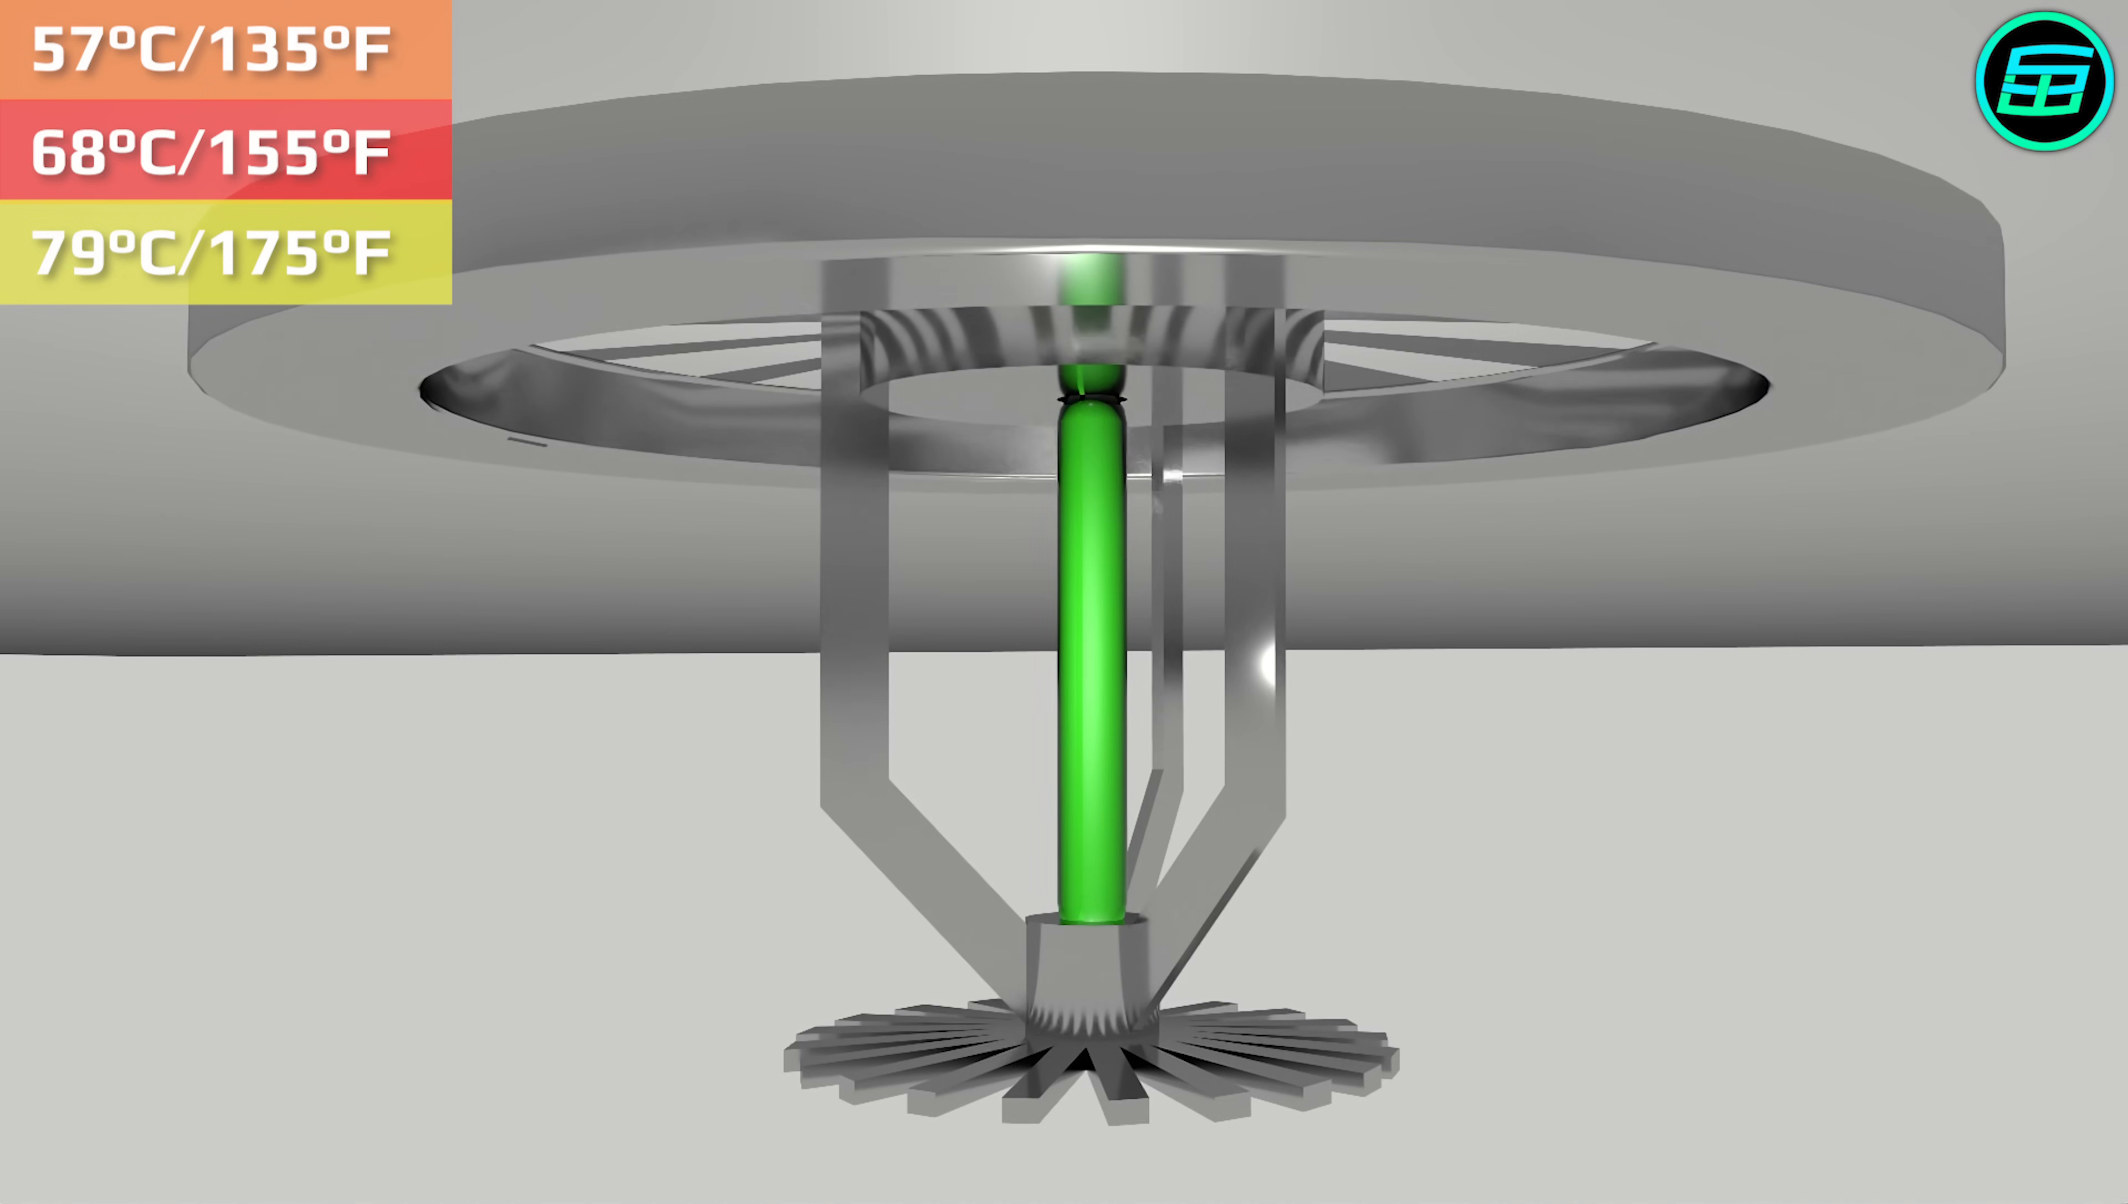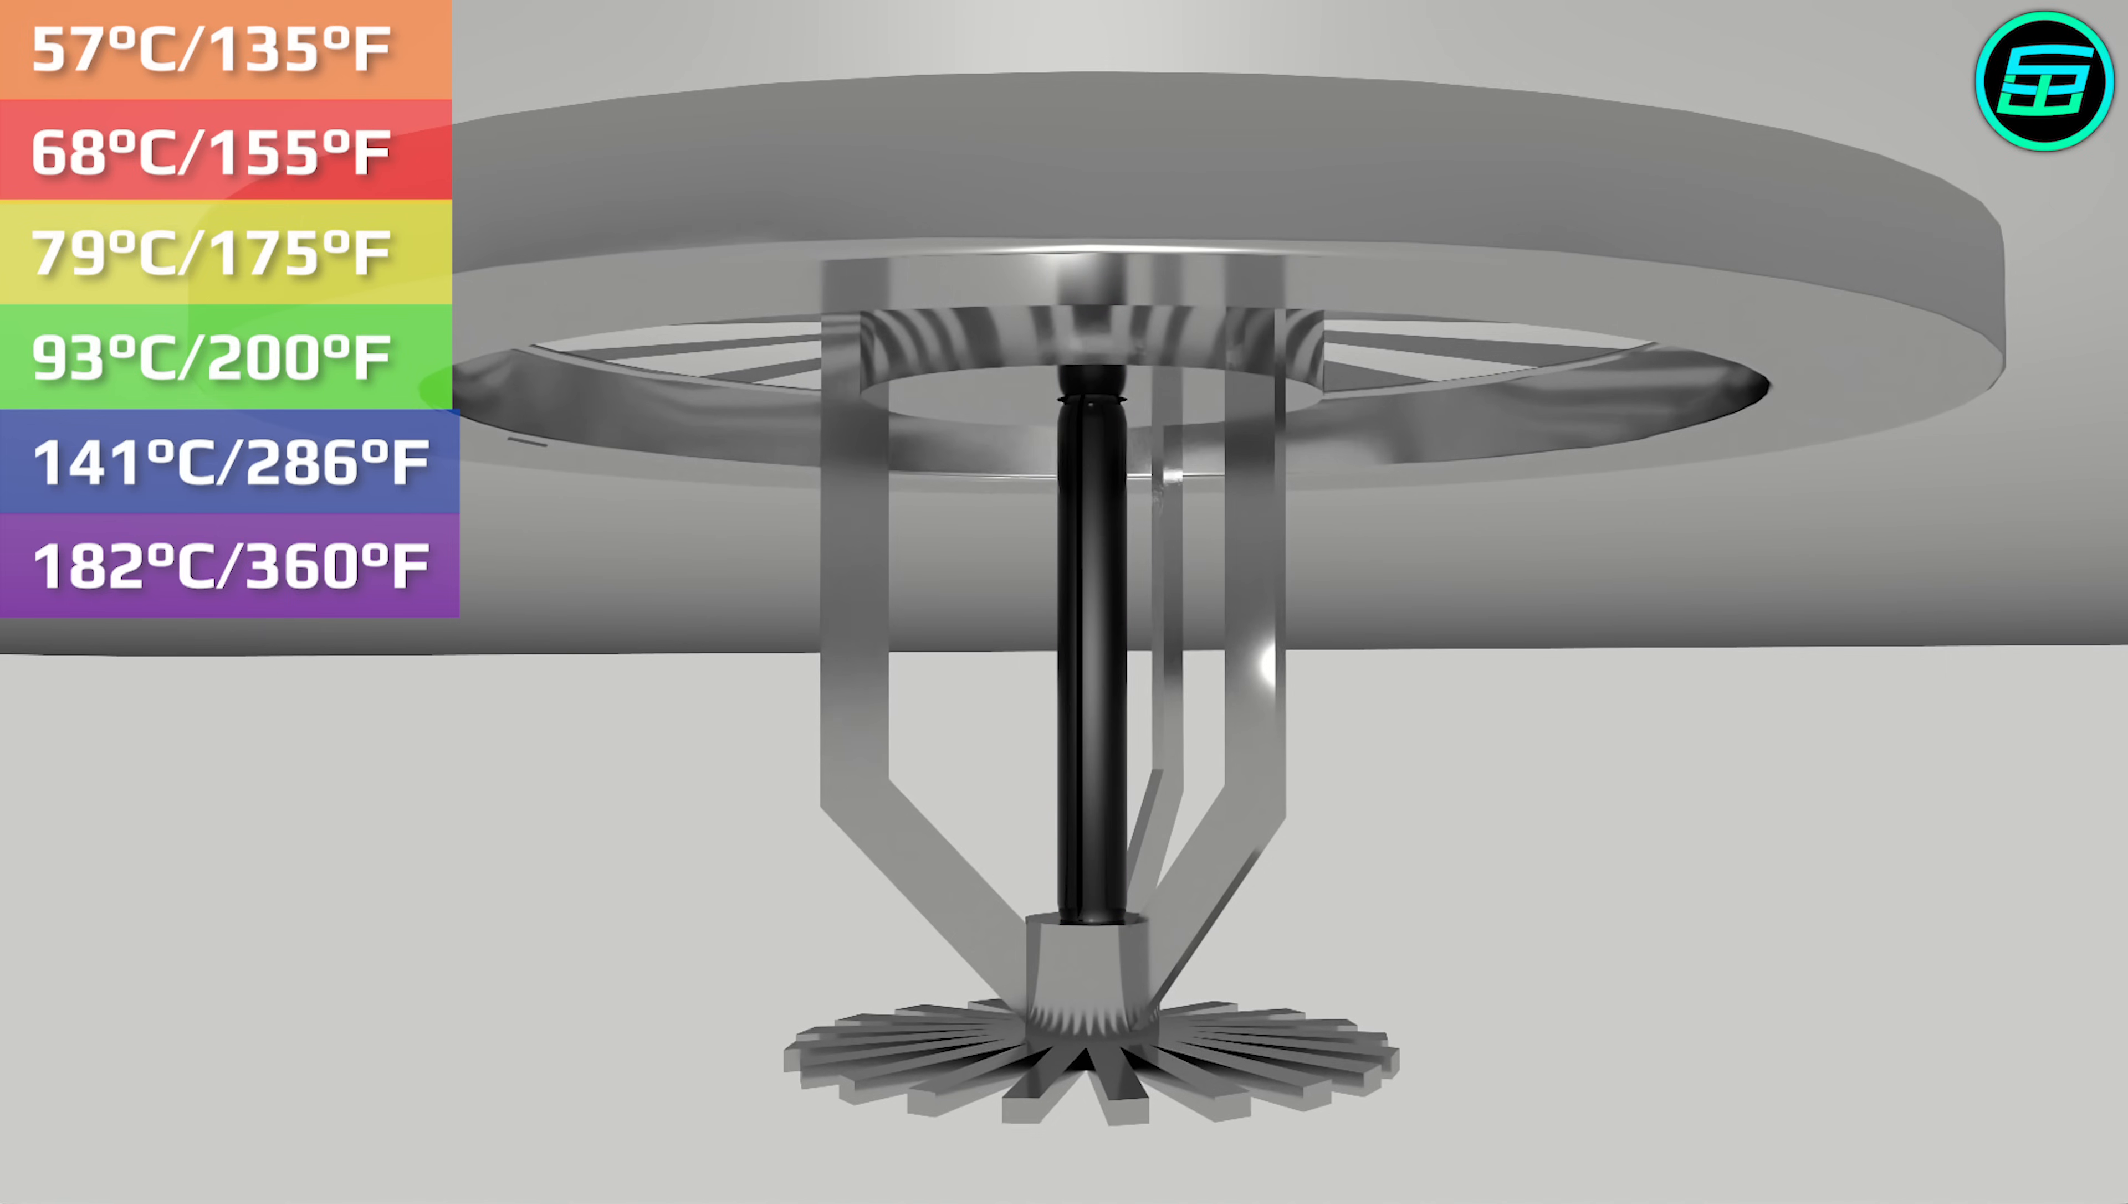Green bulbs 93 Celsius, 200 Fahrenheit. Blue bulbs 141 Celsius, 286 Fahrenheit. Purple bulbs 182 Celsius, 360 Fahrenheit. And black bulbs 227 Celsius, 440 Fahrenheit.